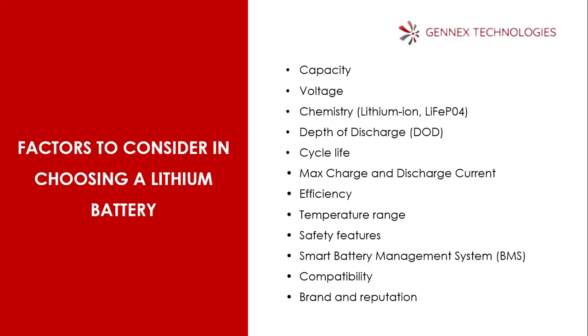So, compatibility. You check your system. Is your system compatible with the lithium-ion battery you want to use? Or is the lithium-ion battery compatible with your inverter? Because it's not every inverter that is compatible with lithium-ion. They are just coming up with different designs now. In those days, they were not compatible. That's why when lithium-ion battery manufacturers started, they had a very wide range, such that some inverters could fit in. But then a lot of information from here and there said some lithium-ion batteries caught fire, and so people were scared. But now a lot of measures have been put in place to make sure that the batteries are safe. The inverter that you want to use with it, you have to be careful to check compatibility, make sure that everything will work well. The brand and the reputation of the manufacturer or the brand name is important as well.